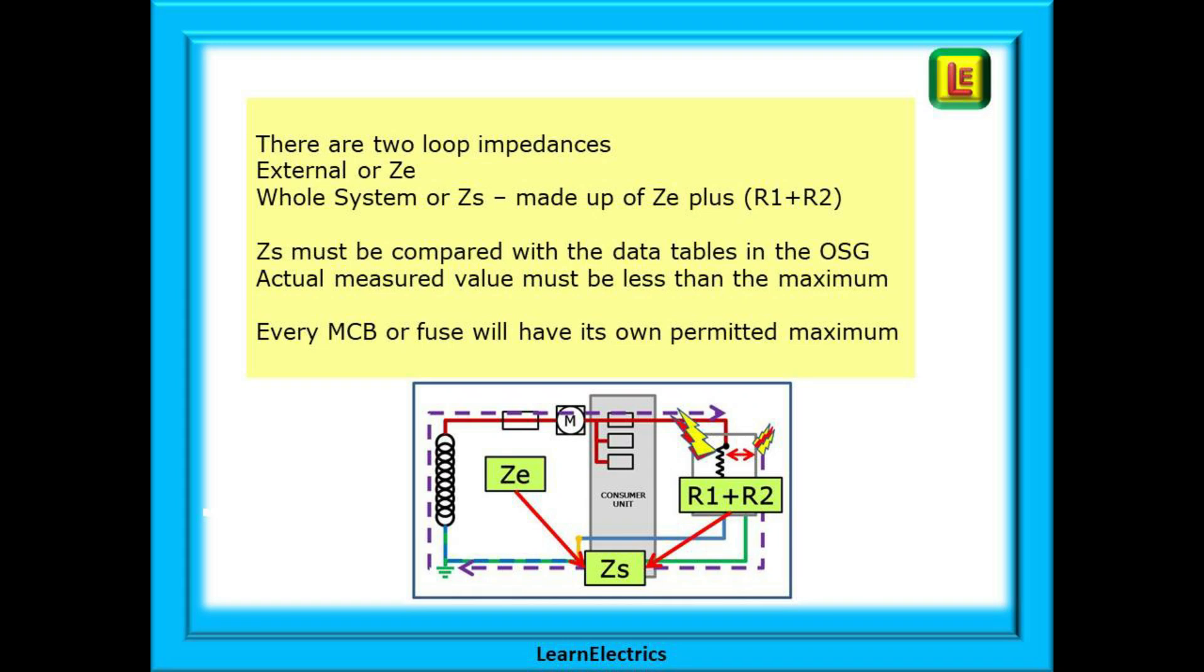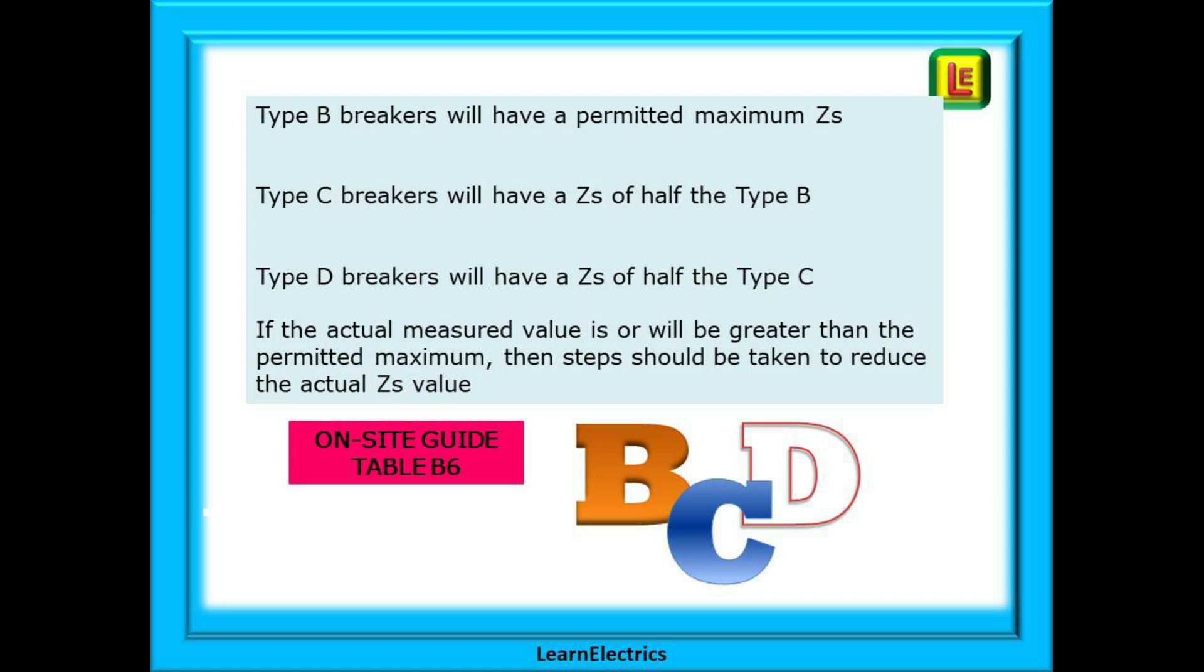There are two loop impedances. All the external parts called ZE the external loop impedance and the whole system is called ZS the system loop impedance and this is made up of ZE plus R1 plus R2. ZS must be compared with the data tables in the on-site guide to ensure compliance with the requirements for safety and protection from electric shock. The actual measured value must be less than the maximum permitted value in the on-site guide and every MCB or fuse rating and type will have its own permitted maximum values. There are three types of BS EN 60898 circuit breakers and there is an easy to understand relationship between types and ZS. Type B breakers will have a permitted maximum ZS as shown in the on-site guide table B6. Type C breakers will have a ZS of half the type B value and type D breakers will have a ZS of half the type C numbers.